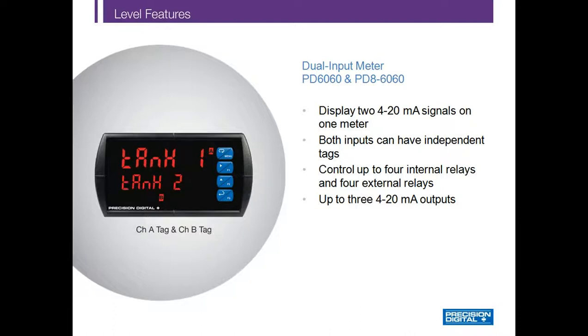A slight variation on dual scale is dual inputs, which can be handled by the PD6060 and its explosion-proof version, the PD8-6060. These two meters can accept two different 4 to 20 milliamp inputs and display them on the upper and lower display. In this case, the upper display shows the value for Tank 1 at 14.24, and the lower display shows Tank 2 at 19.85. Any relay or 4 to 20 milliamp output can be assigned to either input. Overall, the dual input meters provide an economical way to display the level of two tanks, especially in the explosion-proof versions.